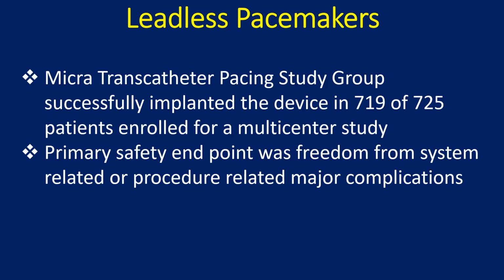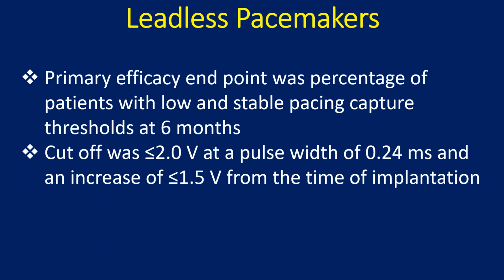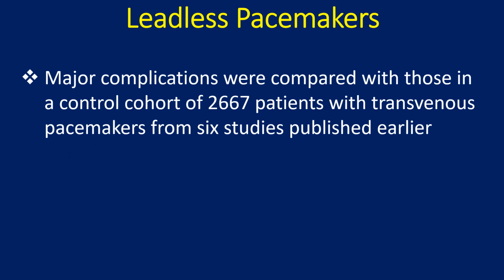Primary safety endpoint was freedom from system-related or procedure-related major complications. Primary efficacy endpoint was percentage of patients with low and stable pacing capture thresholds at 6 months. Cutoff was 2 volt or less at a pulse width of 0.24 milliseconds and an increase of 1.5 volts or less from the time of implantation. Major complications were compared with those in a control cohort of 2,667 patients with transvenous pacemakers from 6 studies published earlier.